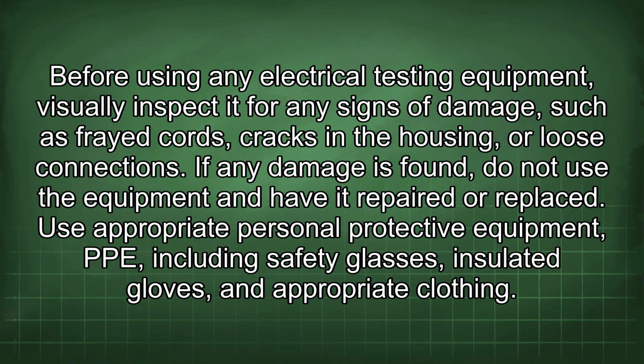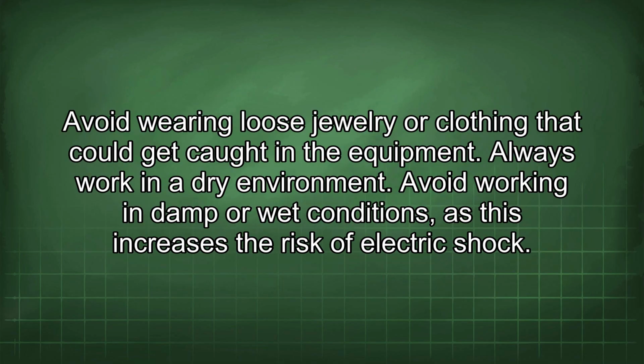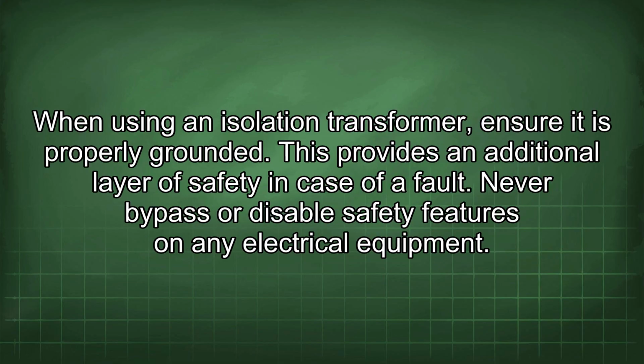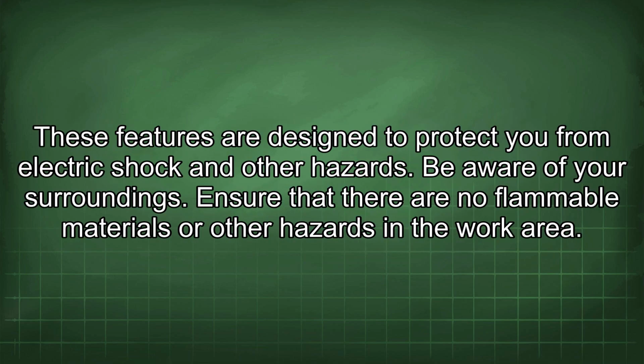Use appropriate personal protective equipment, PPE, including safety glasses, insulated gloves, and appropriate clothing. Avoid wearing loose jewelry or clothing that could get caught in the equipment. Always work in a dry environment. Avoid working in damp or wet conditions, as this increases the risk of electric shock. When using an isolation transformer, ensure it is properly grounded. This provides an additional layer of safety in case of a fault. Never bypass or disable safety features on any electrical equipment. These features are designed to protect you from electric shock and other hazards.